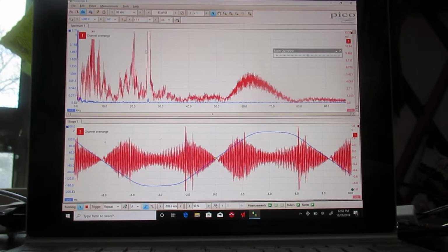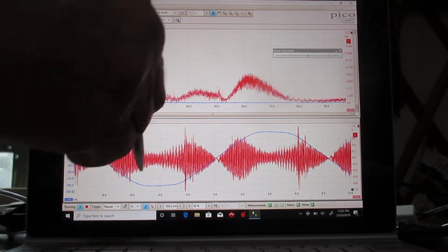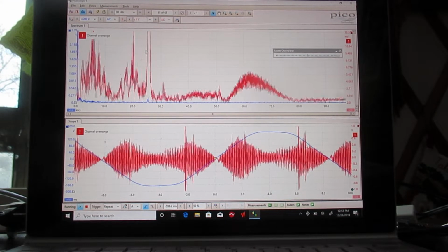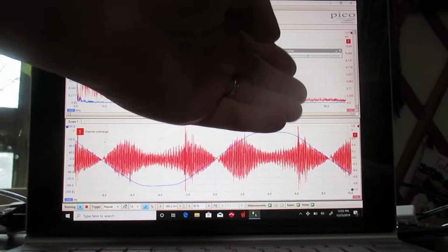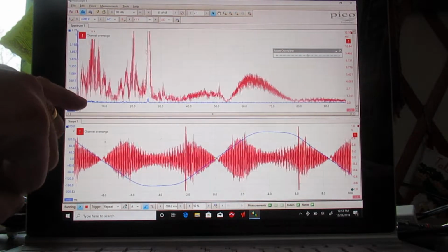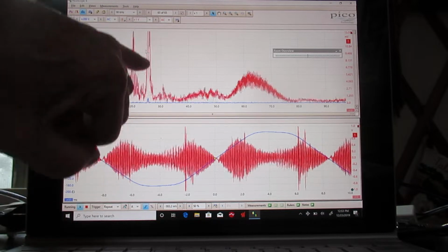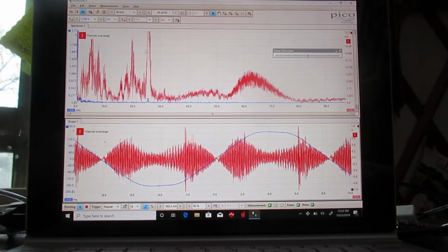This one happens to be a Mitsubishi manufacturer. And we're seeing the normal 60 cycle line right here. And then we're seeing the red dirty electricity high frequency voltage transients. We've got over a volt peak to peak. I could spend more time and zero that in, but we're getting a lot of spikes under 10,000 cycles per second, at 20,000 cycles per second, at 26,000 cycles per second, and a bunch out here between 60 and 70.